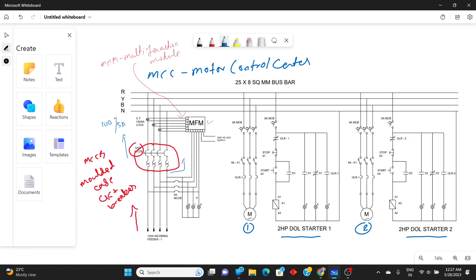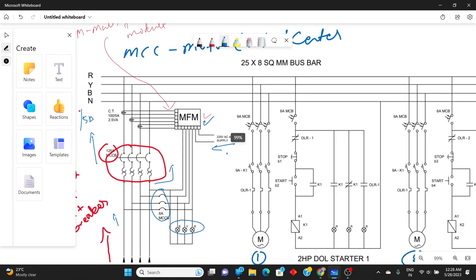In the control panel, we have main power indicators for R phase, Y phase, and B phase — three indicating lamps. There is also one MCCB for the MFM panel so that if any maintenance is needed, or if anything goes wrong on the supply side, this MCCB will trip. To operate the MFM panel we need an external auxiliary power supply.